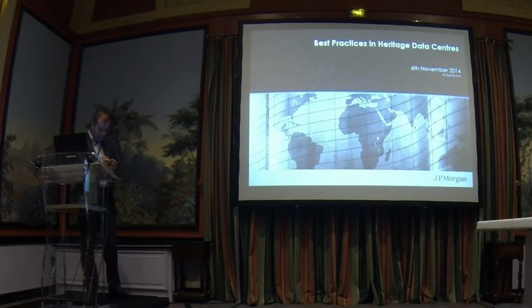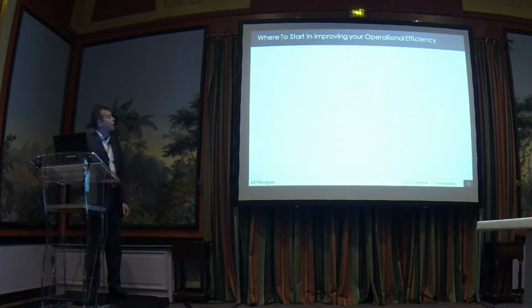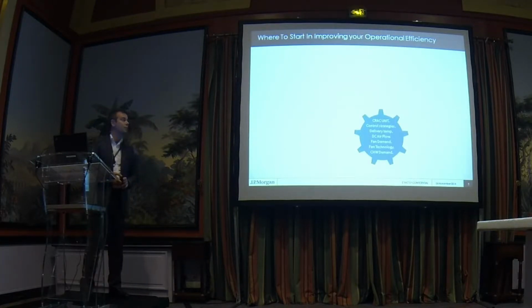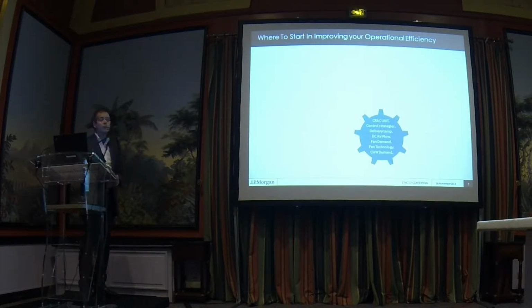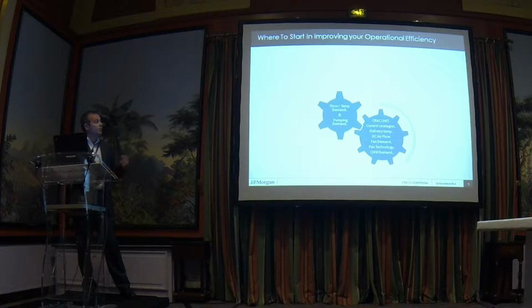So basically, we're going to go through how to improve your data center. Say you've got an old data center, and there's not many things you can do these days without spending a lot of money. Some of the easy wins that are hanging around in just about everyone's data center are the CRAC unit controls, the delivery temperatures, DC airflow, fan demand technology, chilled water demand. And then the next stage up is flow and temperature control and pumping demand, chiller staging and set point control.